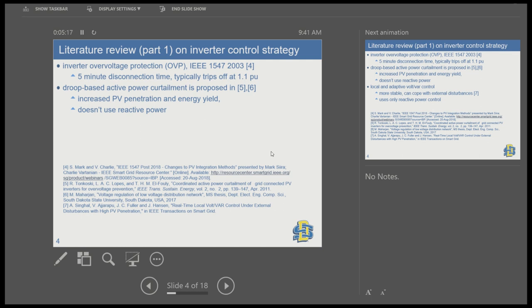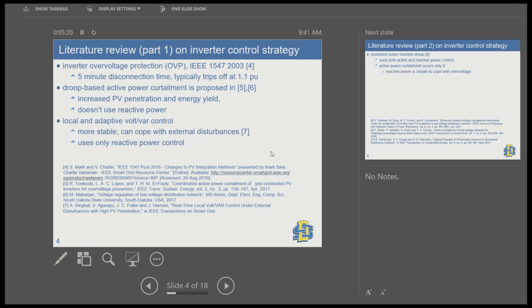Another approach is local and adaptive Volt-VAR control. Volt-VAR control is popular in that it uses reactive power to lower the voltage. In one paper, they propose an adaptive Volt-VAR control that can mitigate some of its disadvantages. But it only uses reactive power control, which is sufficient to prevent overvoltage only at certain levels of PV penetration. At very high PV penetration, reactive power alone may not be sufficient.